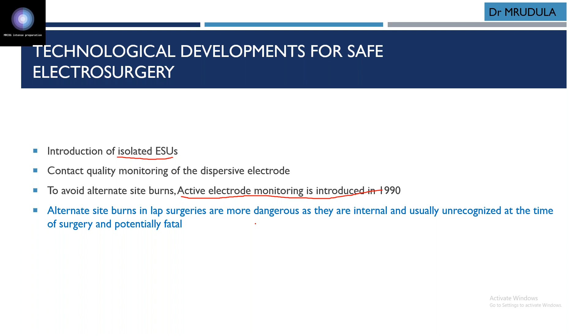So this is the active electrode monitoring. What happens with it? They are specific instruments. They have two extra coaxial layers, a conductive shield and a second outer insulation layer. All these fit in a 5 mm cannula. A circuit is established between the conductive shield, the active electrode monitor, and the ESU. Here you can see this is the active electrode monitor unit, this is the ESU, and there is a connection in between these two and this instrument.